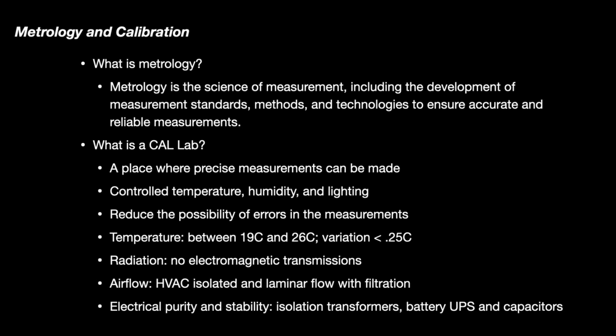What's a Cal Lab? A Cal Lab is a place where precision instruments can be made. It's controlled with temperature, because temperature is the enemy of voltage measurement. And voltage measurement is the key to everything else that happens. Amperes, resistance, todo. You want to reduce the possibility of errors in measurement by calibrating instruments.